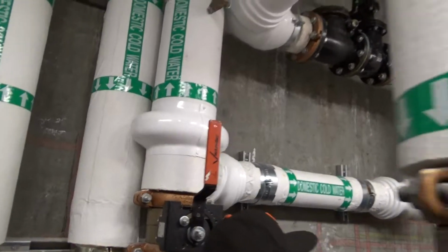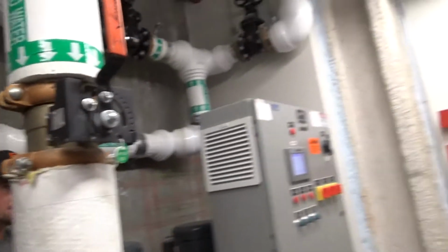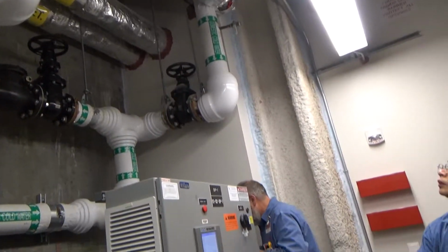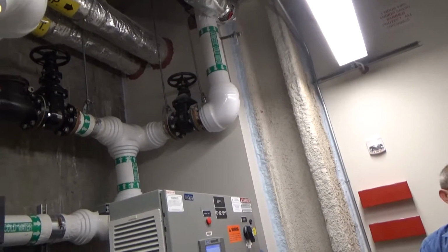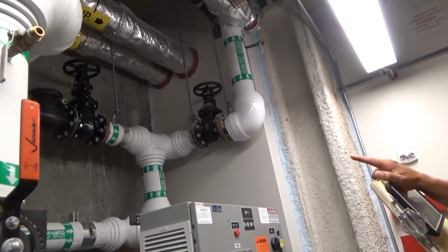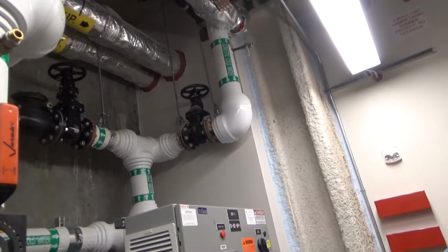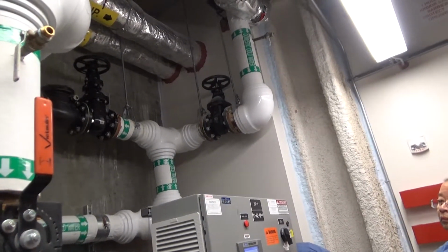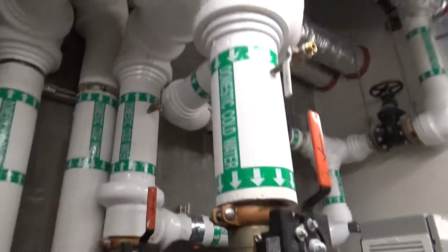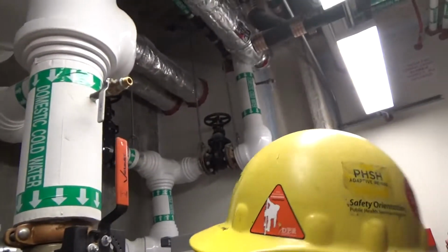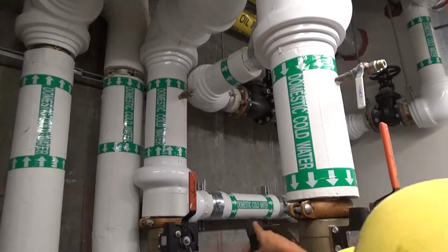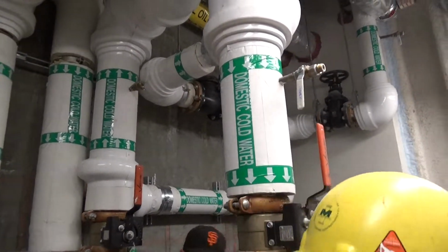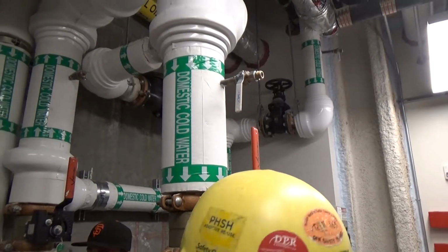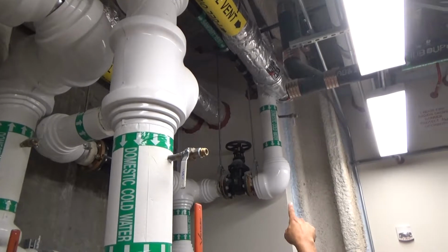Okay. Is the rotation... It can be either, because it's a bypass of the pump from the city or from the... So if you isolate your pump, see, same with those, could be either way. Hey, look, this does a U-turn, it goes up and then it comes back this way, and then the arrows are going in the opposite direction. Yes, so it's part of the emergency bypass system. This could actually go both directions. So if you isolate this skid out, that pipe right there is to your emergency water tanks.